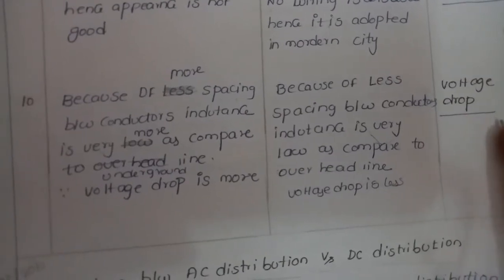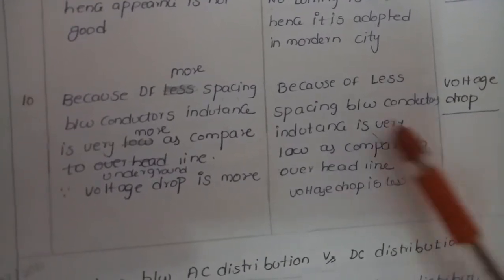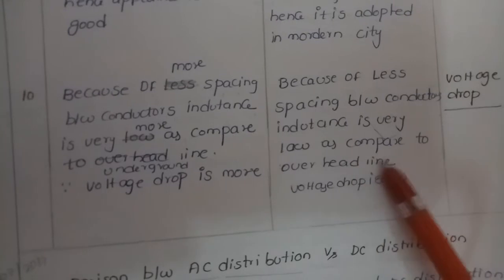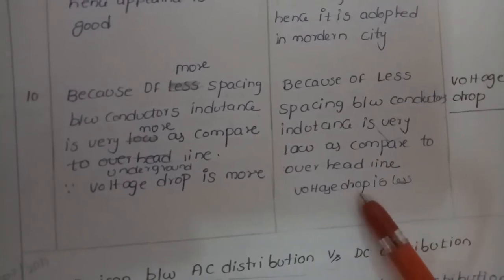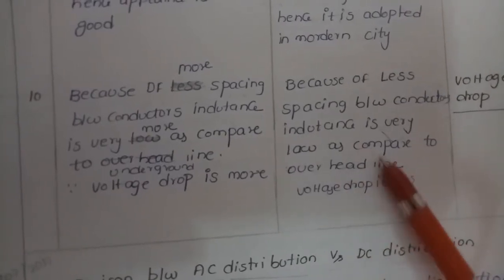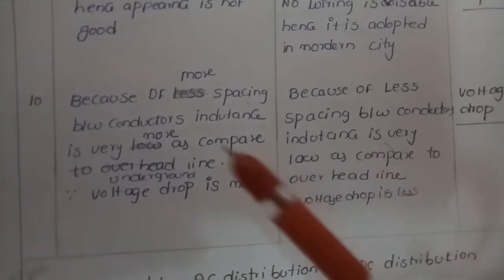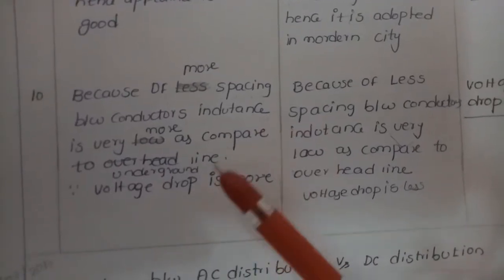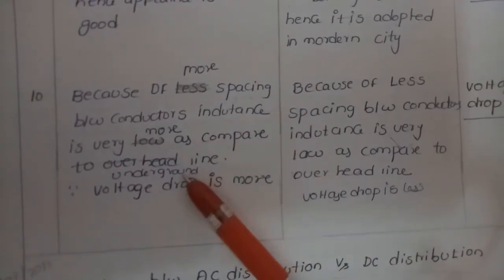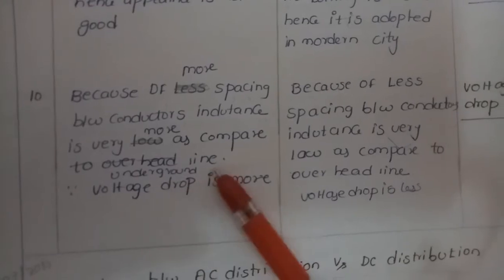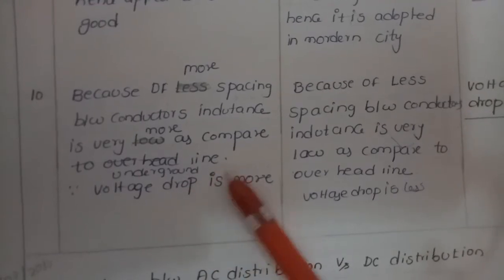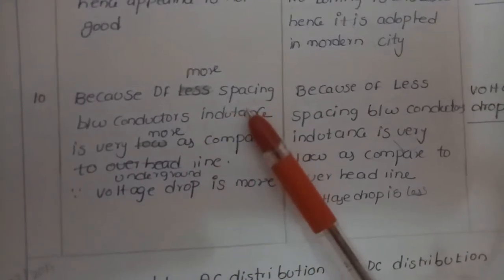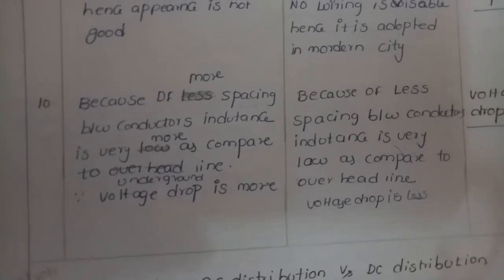Regarding voltage drop, because of less spacing between conductors, inductance is very low in underground systems compared to overhead lines, so voltage drop is less. In overhead systems, inductance is more compared to underground lines, and therefore voltage drop is more.